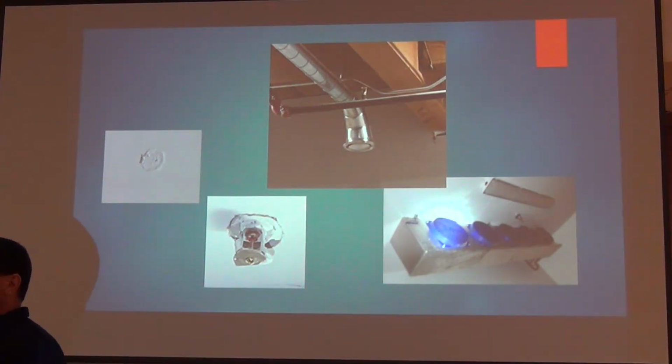Okay, so in this one, it wraps around better when it's going vertically than it does horizontally. Horizontally, it's gotta be further away. Vertically, on some heads, and depending upon the size of the pipe, it can be up to 4 inches away. And if that head is not right in the center of the spiral duct, at what point do you believe the spray of the head is gonna be over top of the duct? Does it have to be above the top of the duct? It does not have to be if that head is less than 18 inches down.